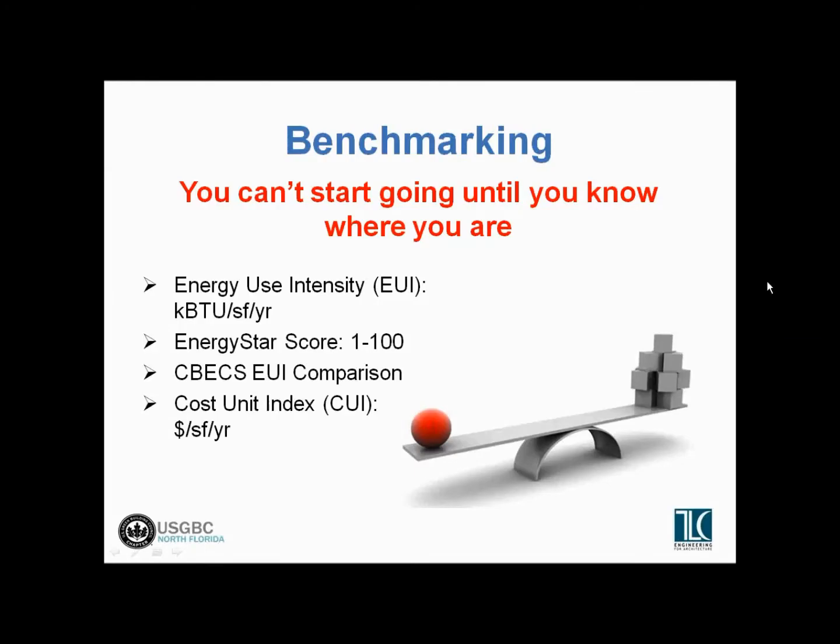So as I said, benchmarking is an important first step. Whether you identify your building's energy usage on an absolute value, like kBTUs per square foot per year, which is an energy use intensity, or using a database of other similar buildings to compare it against, like CBECS or Energy Star.